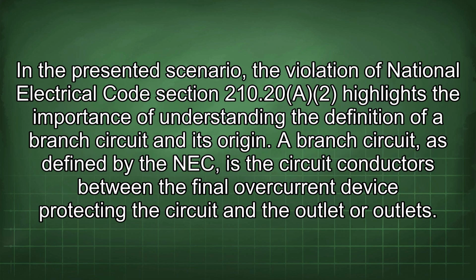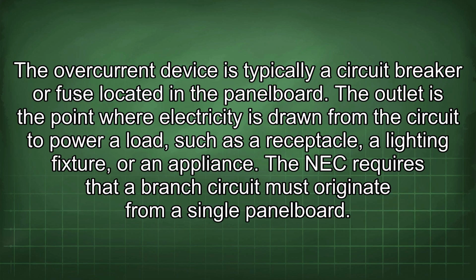In the presented scenario, the violation of National Electrical Code Section 210.20(A) highlights the importance of understanding the definition of a branch circuit and its origin. A branch circuit, as defined by the NEC, is the circuit conductors between the final overcurrent device protecting the circuit and the outlet or outlets. The overcurrent device is typically a circuit breaker or fuse located in the panelboard.